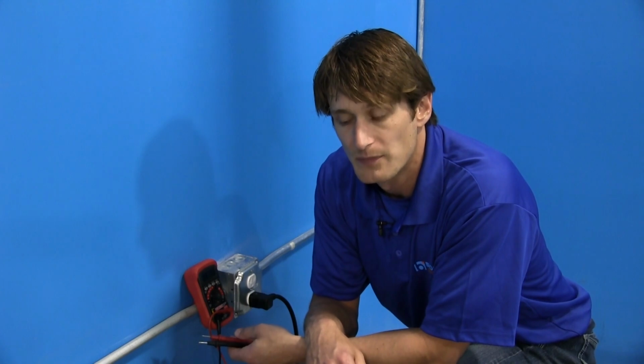One of the first steps is testing the wall voltage to ensure that you have the proper operating voltage. Testing your wall voltage is very important to ensure that your system is operating at the proper voltage. You also want to ensure that your system is on its own dedicated outlet specific for this system.